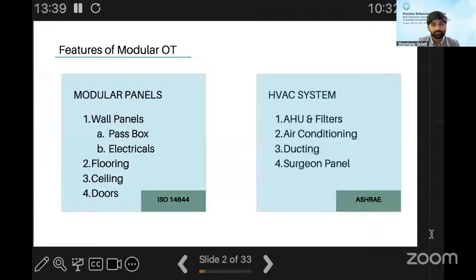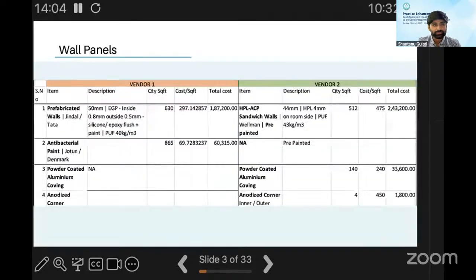So a modular operation theater is a prefabricated structure which is designed with seamless and non-porous surfaces, hermetically sealed doors, and a dedicated air handling unit. What is important is that all these components should follow certain standards, such as the ISO 14644 standard for your surface and the ASHRAE standards for the air handling system.